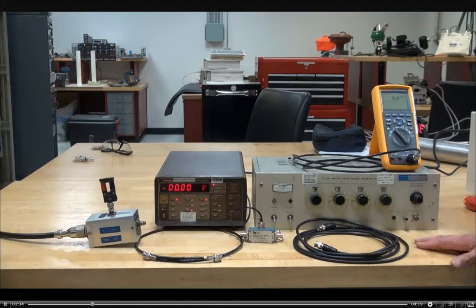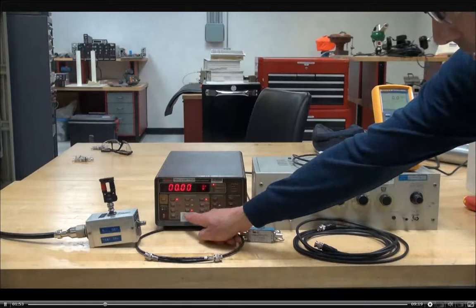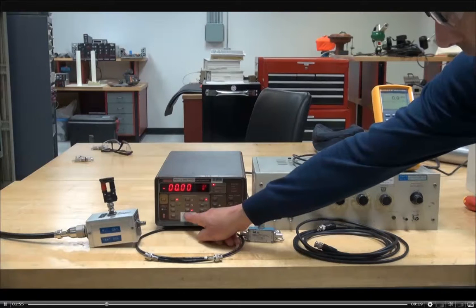Alright, so we have a wooden desk here in the shop. You'll probably be using a plastic cart, so that would satisfy for that. Okay. There's a note, when scaling the electrometer, the auto range feature is recommended for performing the multiple measurements that follow. Alright, and as you can see here for the electrometer, the red light is on for the auto mode.